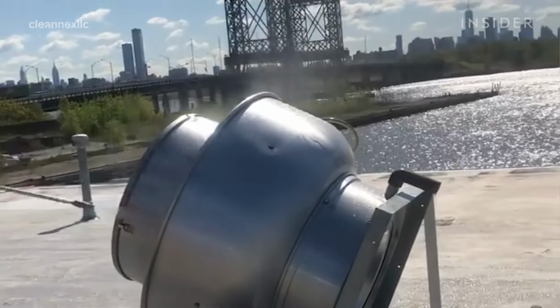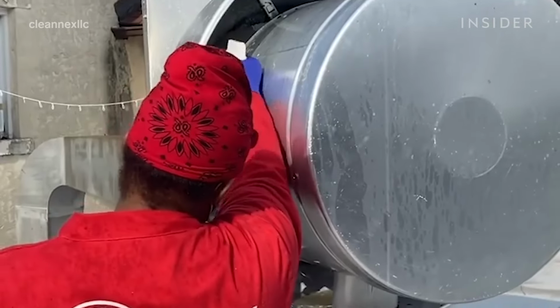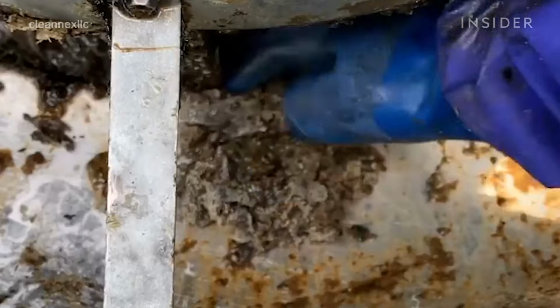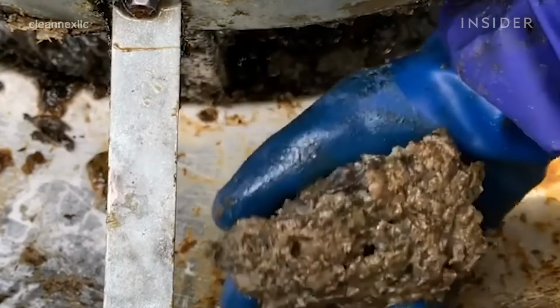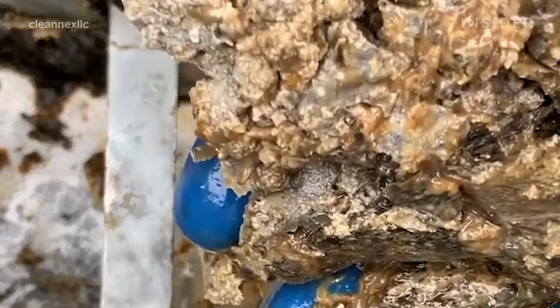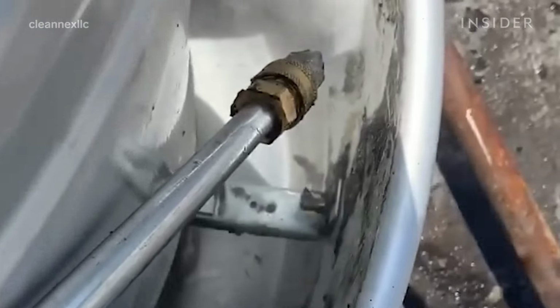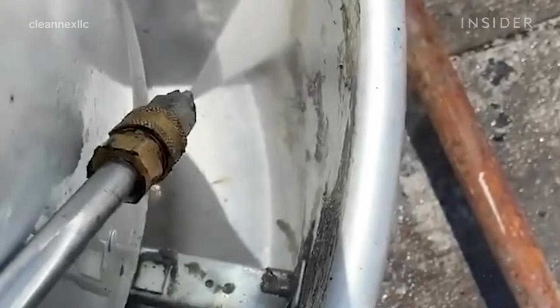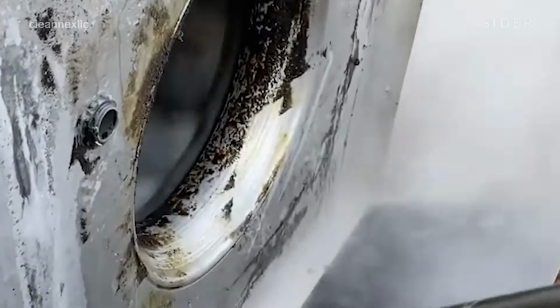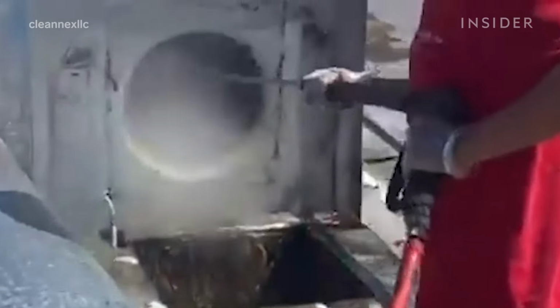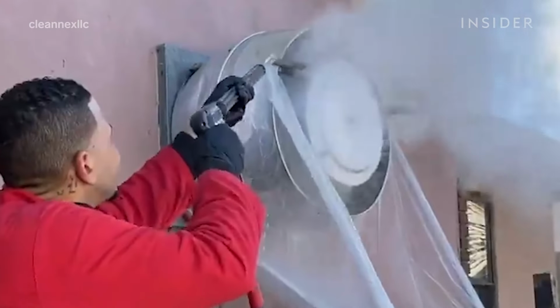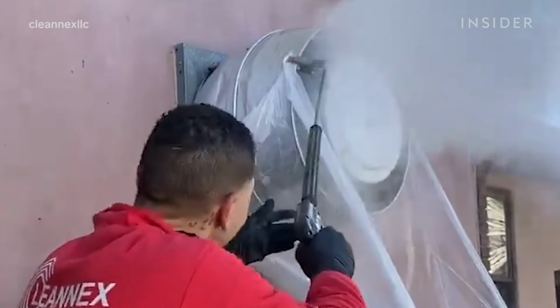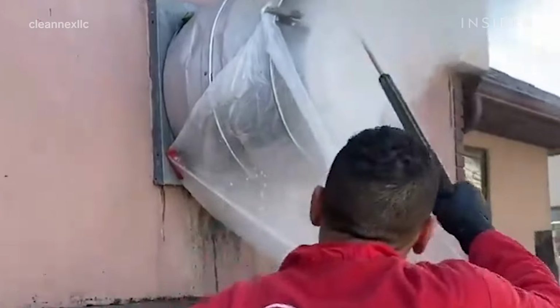Everything is cleaned from top to bottom. You would start cleaning the fan first. We're using a high-end degreaser with a little potassium hydroxide and sodium hydroxide. Those two chemicals combined create miracles in destroying the fat and the grease. In our case, we time it somewhere between 10 to 15 minutes. Once we see that the grease starts to melt, at that point we know we need to apply hot water and remove it. Because anything longer at that point is going to start to destroy the metal.